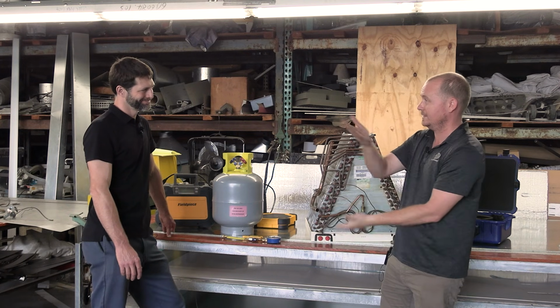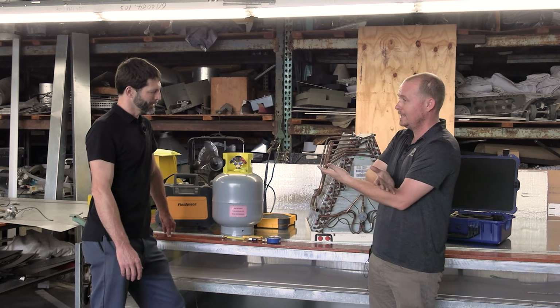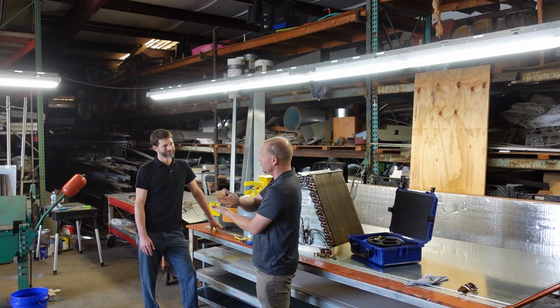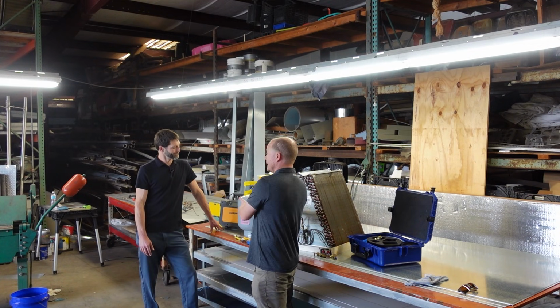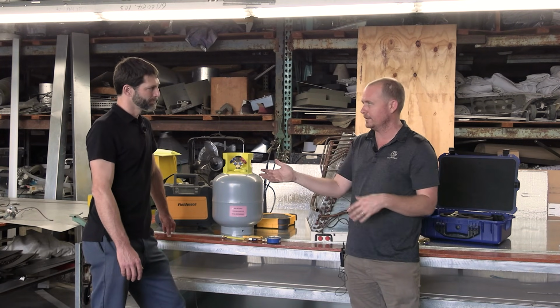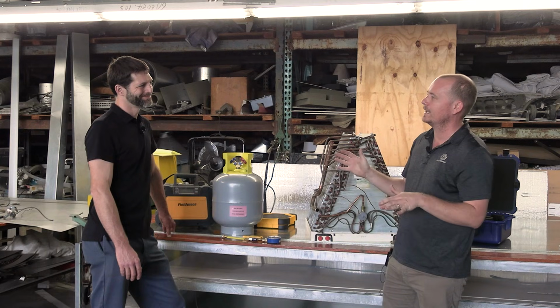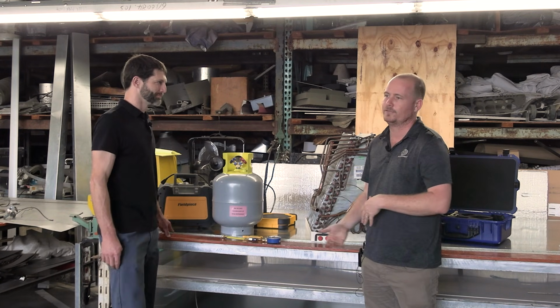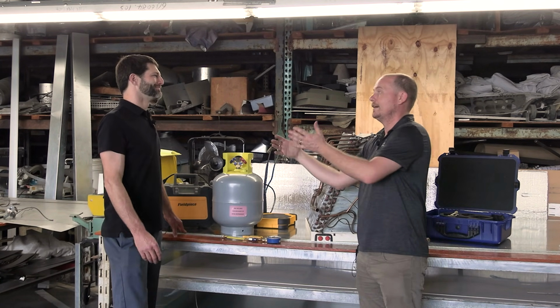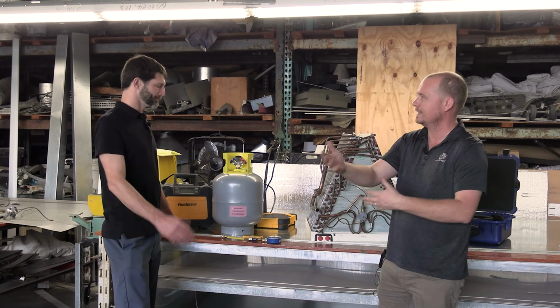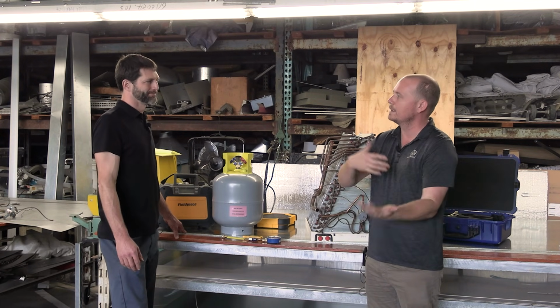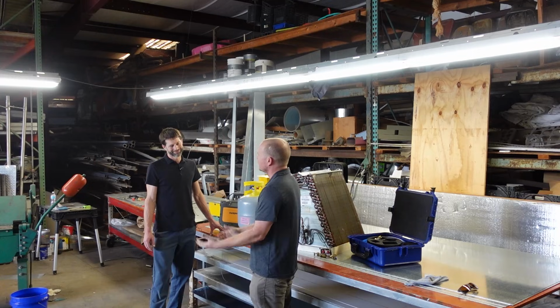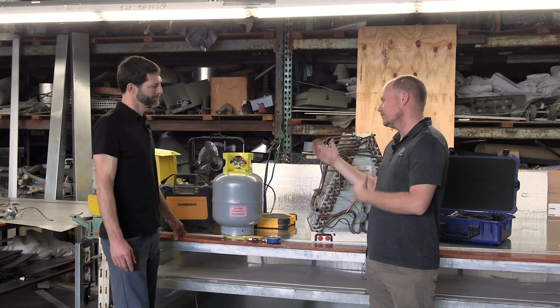If you're doing the opposite, if you're trying to put refrigerant into the system under low ambient conditions, then you do the opposite, right? You try to keep the tank warmer. You could use a heating blanket or something if you're charging. So just thinking about that can be helpful. Same thing is true of vacuum. If you're trying to get molecules out of the system, then heating the compressor with a heat gun, or the accumulator where there might be some refrigerant entrained in the oil and stuck, can be helpful. So always think about that.